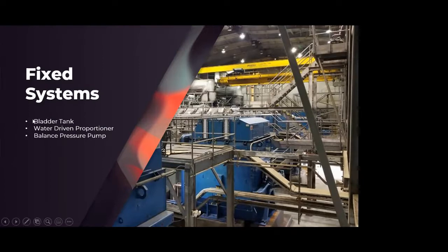The fixed systems. We have three different systems. The first two we use very regularly: bladder tank systems, water-driven proportioners, and balanced pressure pump systems. I can say over the last 24 years, we've really only used one balanced pressure pump system, and it was on a Goodyear rubber tire facility.